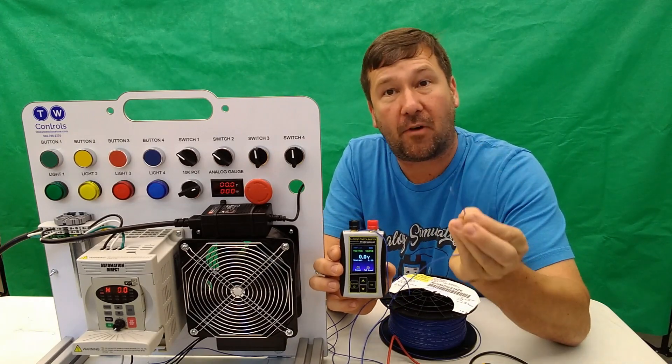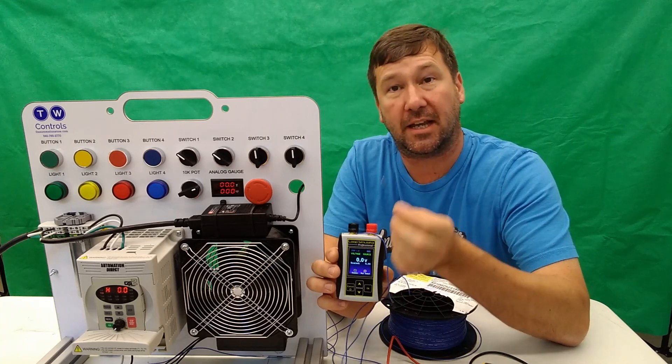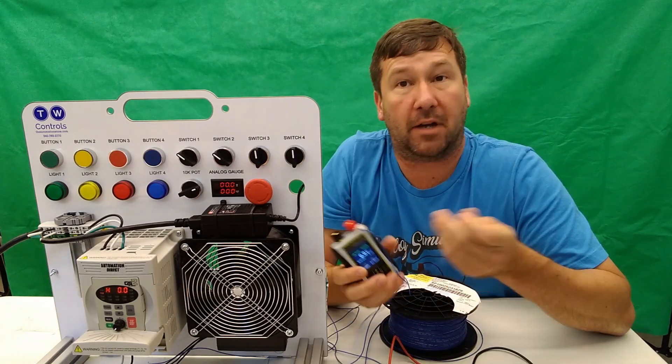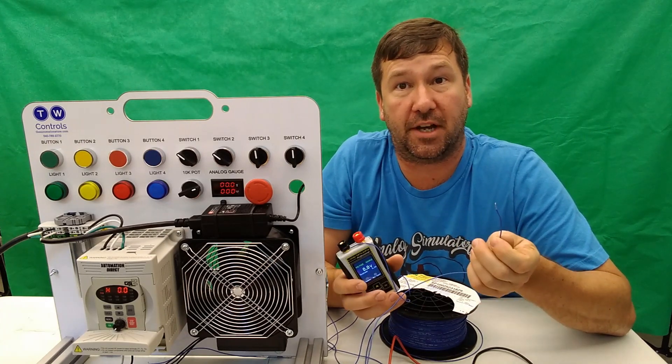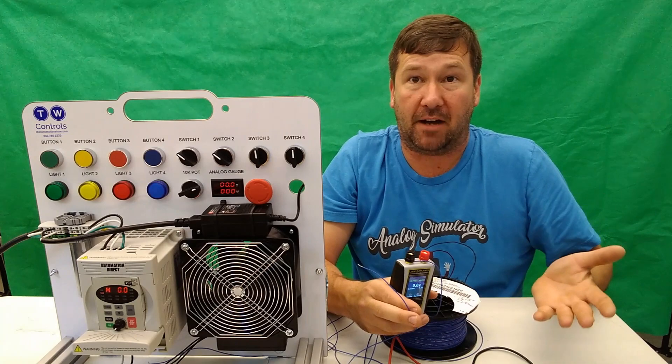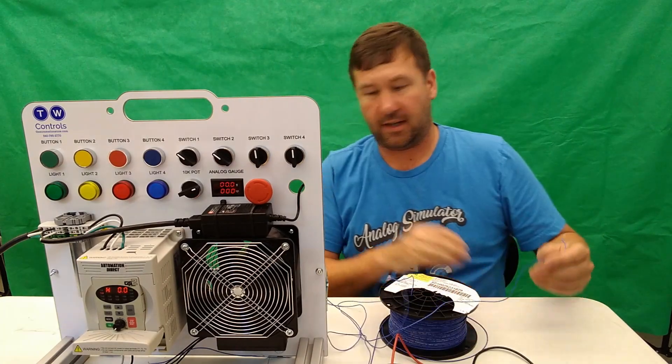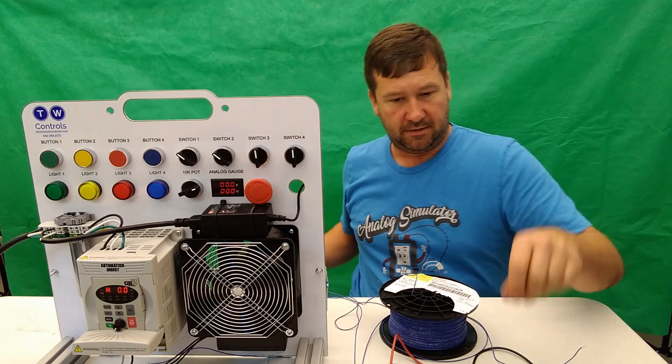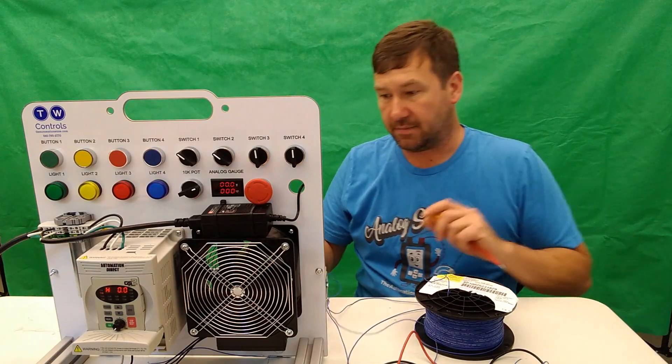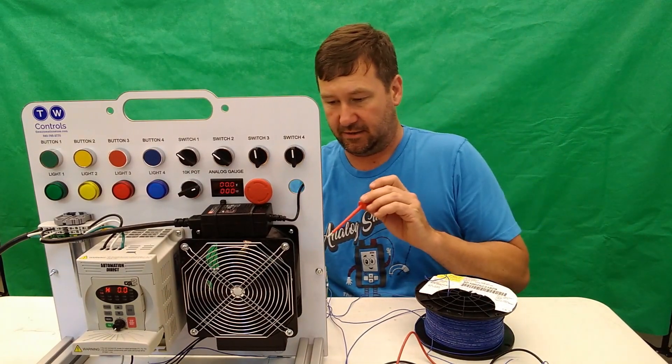But it is a four to 20 milliamp signal. That means it has what they call a live zero. That way if a wire is loose, it'll show zero milliamp when we know then that we have a malfunction in the circuit. Now let's just show how this is going to work with this milliamp signal. So if you'll give me just a second, I'm going to modify our signal to accept a milliamp instead of a voltage signal.